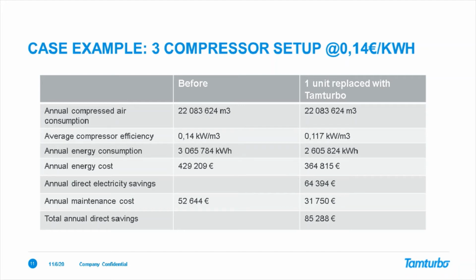with our more efficient compressor taking a bulk of the load because of the good variable load characteristics, then the same amount of compressed air was done with almost 500,000 kilowatt hours less energy. This is directly then as a cost saving 64,000.